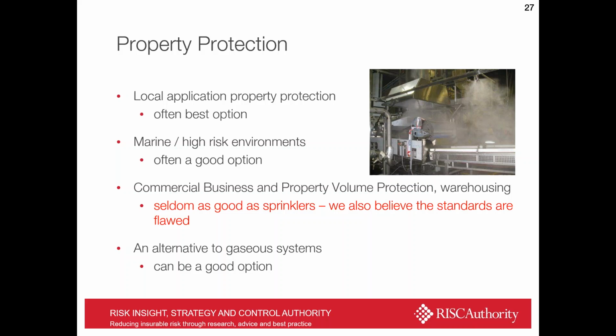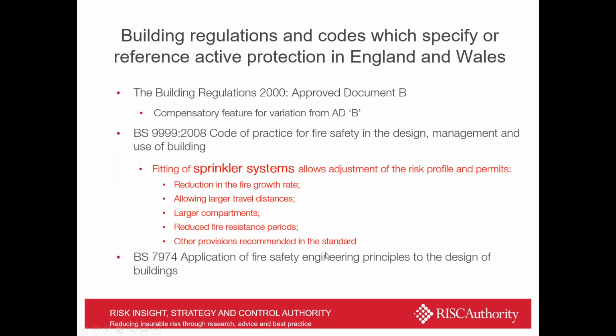But certainly they can also be considered as a practical alternative to where gaseous systems might be deployed. They can be a very good option, subject to the fires being of the right type to play to its strengths. So I won't dwell on this, but building regulations do talk about water systems, generally in terms of sprinkler systems, as we said before. They can be used to compensate in various codes, to reduce the fire growth rate, allow larger travel distances, larger compartments, reduce fire resistance periods, etc., etc.